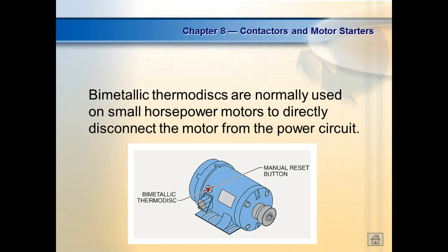We talked about some motors, some single voltage motors have internal overloads. Some of them are resettable, these are really nice. Some of them are actual thermal switches that automatically reset, and those motors can get you into trouble, right? You don't know why. Because you go out there and you've got a motor that's not running, and you have power on your system, you get your hands inside those blades, and all of a sudden it resets itself. But you've got to be careful.